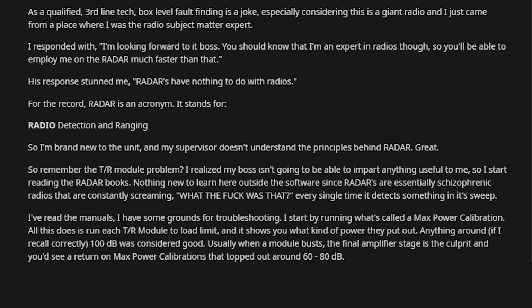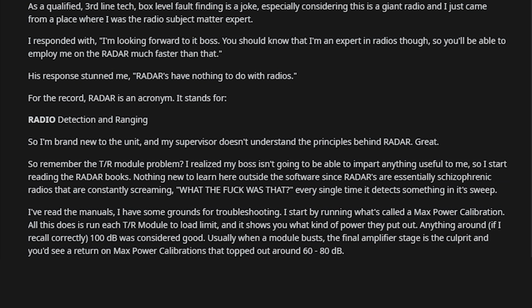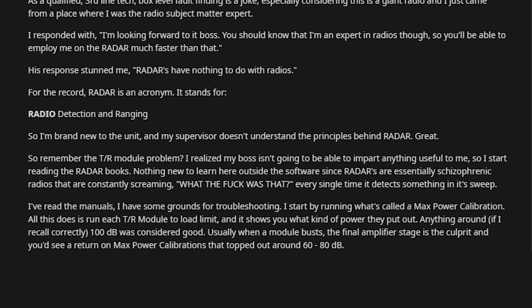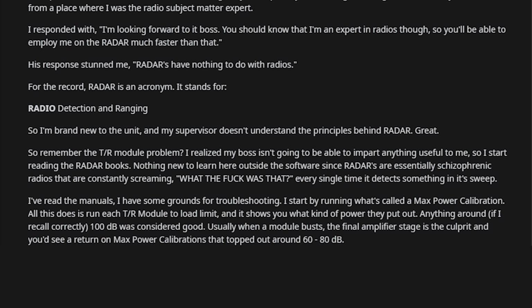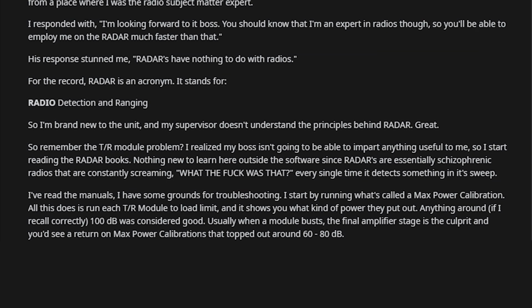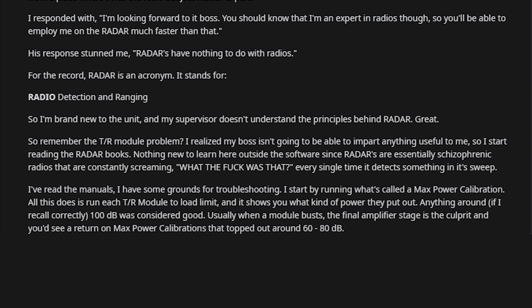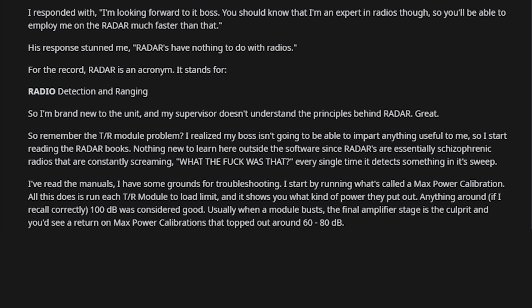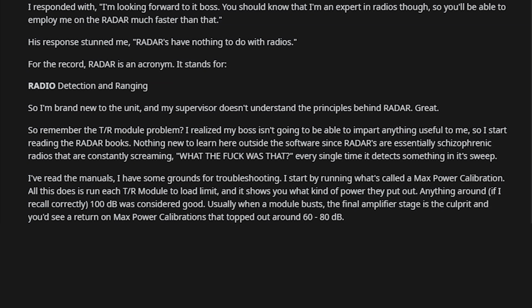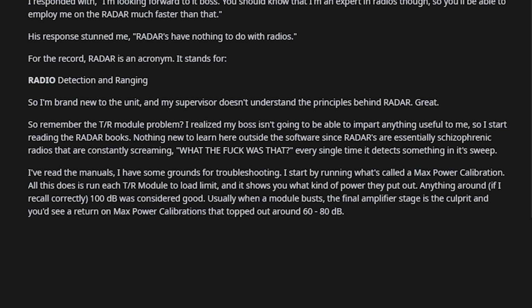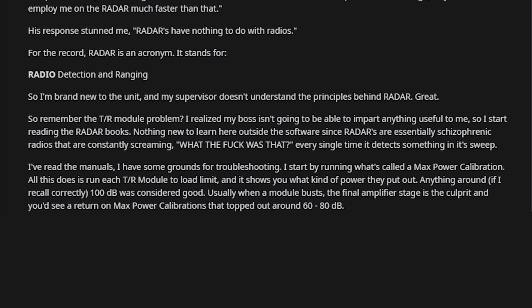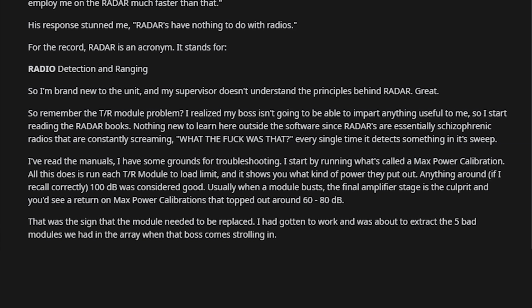I start by running what's called a Max Power Calibration. All this does is run each TR module to load limit, and it shows you what kind of power they put out. Anything around, if I recall correctly, 100 decibels was considered good. Usually when a module busts, the final amplifier stage is the culprit and you'd see a return on max power calibrations that topped out around 60 to 80. That was a sign that the module needed to be replaced.